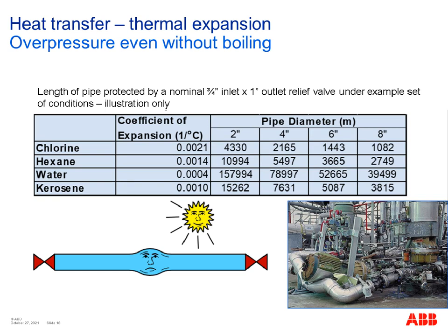So the example on the previous slide, the case study, was based on ammonia being vaporized under heating. But thermal expansion can cause a large rise in pressure even without a change in phase. So this slide shows different thermal expansion coefficients for different fluids. So we've got chlorine, hexane, water, and kerosene. You can work out the coefficient of expansion based on looking at the densities at 2 different temperatures, and you can work out what that expansion coefficient actually is.